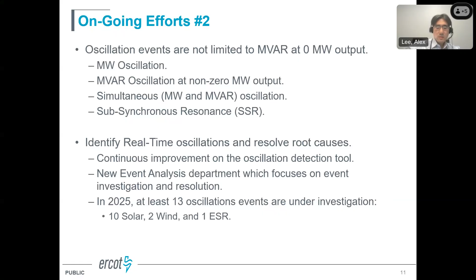So what are some of the lessons learned? Some oscillations are fully resolved through tuning or equipment adjustments, which typically take months of interaction with not just the generator owner or operator, but also the OEM vendors for the plant. For the short term, ERCOT's focus has been to reduce the number of oscillations on the system due to equipment limitations, and as long as ERCOT has the right information and capability submitted by the resources, ERCOT's requirement only extends to that level.